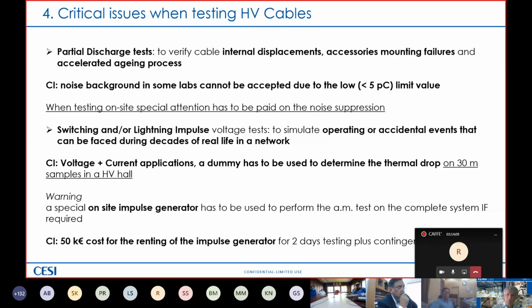And here I put a special warning, because in case a utility asks to perform the test on a complete cable system, that is the 150 meters of the cable loop, you need to use an on-site impulse generator. And just for your reference, a couple of days of renting this on-site impulse generator is about 50,000 euro. And you are on site. It means that if you have rain, you have to stop, and another 2 days have to be considered, and so on and so on.